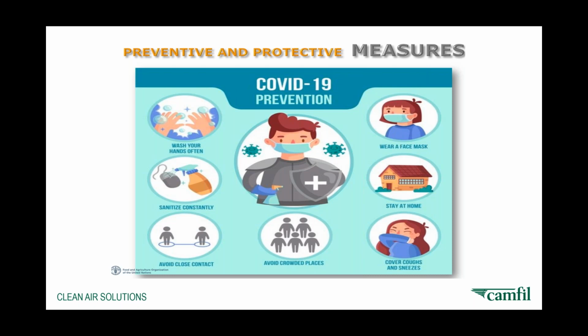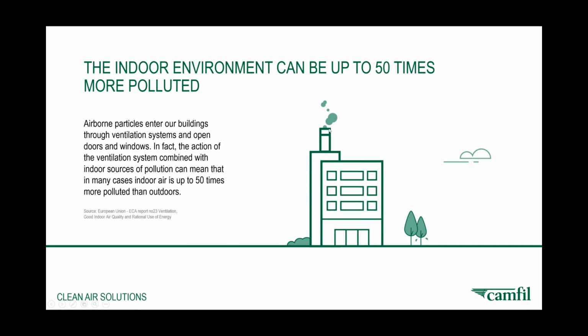And many of us spend most of our time at present indoors. And unfortunately, whether it's during this crisis or in general, once we're indoors, the indoor environment can be up to 50 times more polluted. Everybody here in the ASHRAE Association is dealing with ventilation, dealing with filtration, and dealing with indoor environments. So airborne particles come into our buildings typically through open windows, etc., but also through ventilation systems. And what we're doing is actually concentrating pollutants from the outside air. So you need to be careful with the ventilation systems and ensure the correct level of filtration is used to catch and trap those various pollutants.